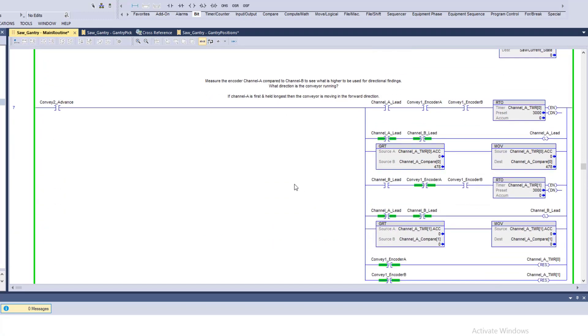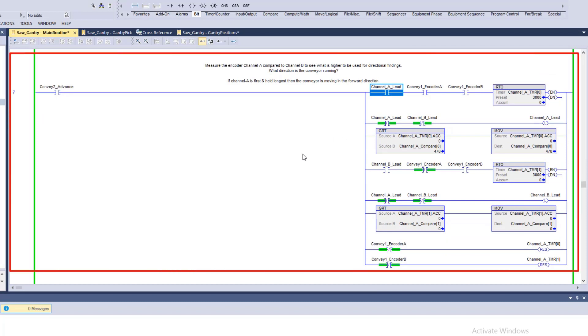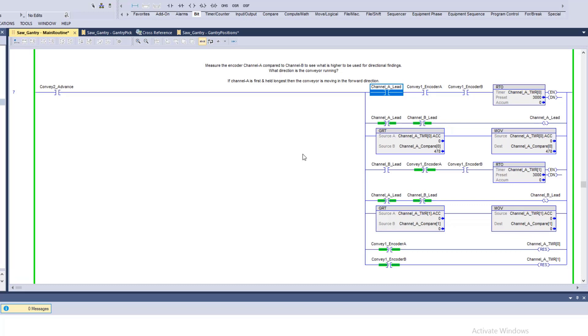The logic here determines encoder count direction. With an encoder you have an A channel and a B channel — they are 90 degrees out of phase. If the A channel leads and B comes in second, the conveyor is running in the forward direction. If B comes in first and A comes in second, the conveyor is running in reverse.